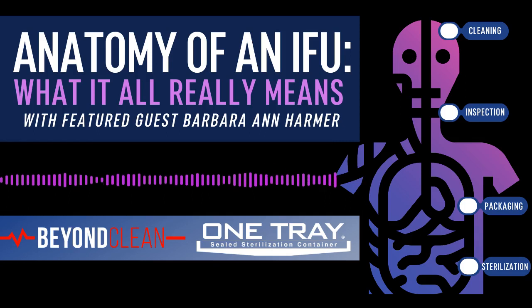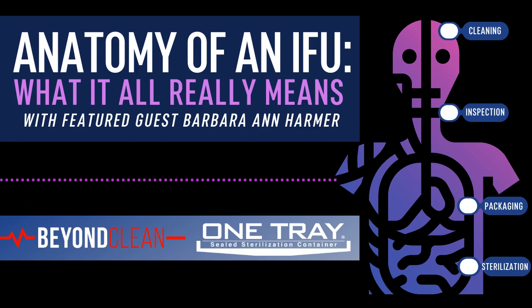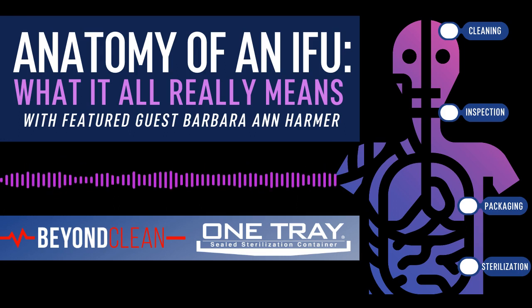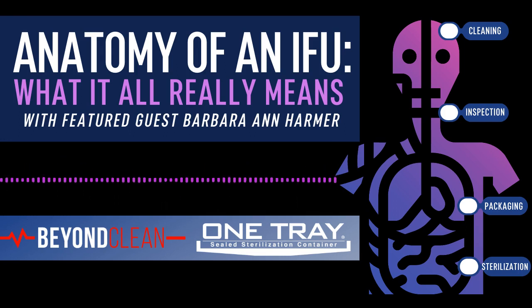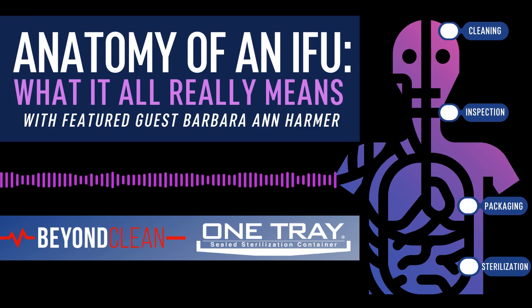Okay, so we're going to say now a different instrument or device, and in this case, it was validated in the ONETRAY, but you're going to sterilize it in sterile wrap. I'm going to throw a curveball at you. How does this one play out? Okay, so now we've been validated in ONETRAY, and we're going to put it into sterile wrap. Sterile wrap is the packaging system, and in the IFU of the sterile wrap, it will tell you that you do need dry time. So even though it was validated in ONETRAY where there is no dry time, you've now changed the packaging system, and sterile wrap requires dry time according to their IFU.